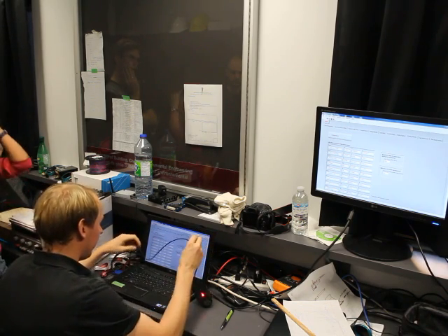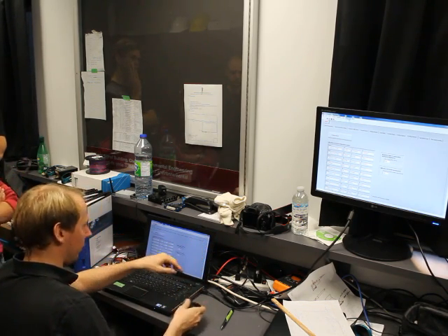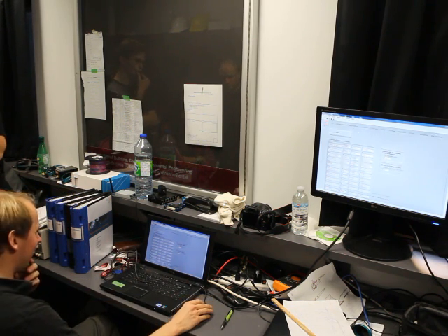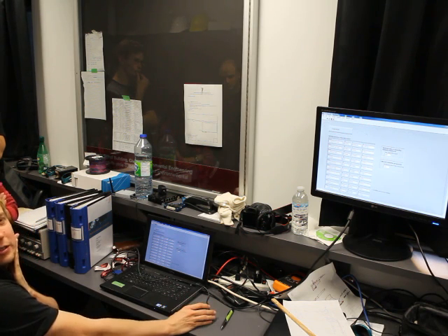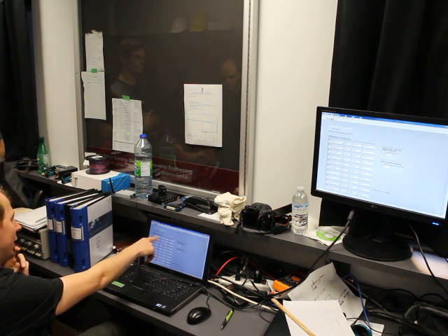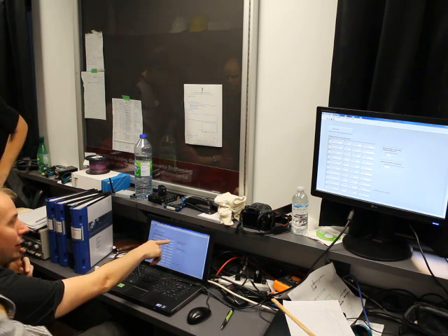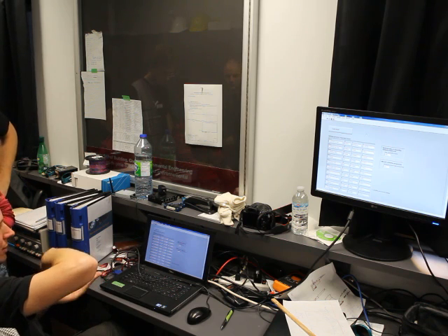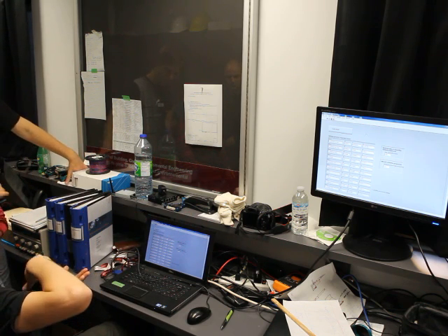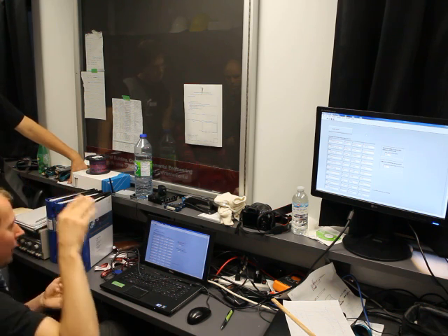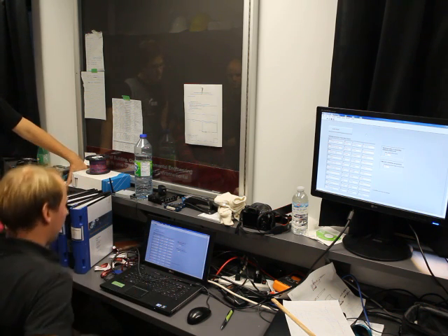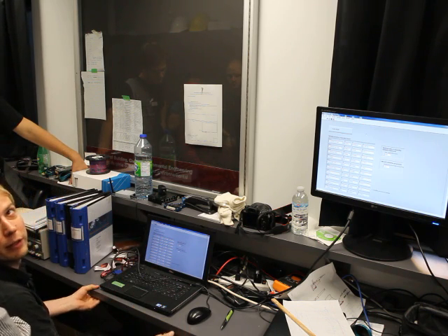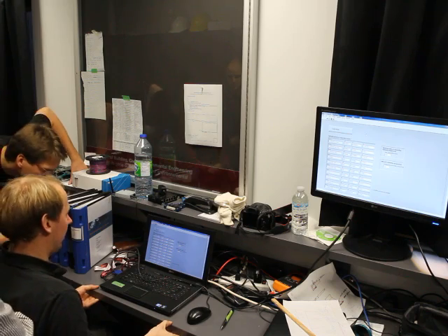What is also maybe important is we already talked a lot about calibration. You can calibrate your sensors, and what will come up is a value for R0, A, and B. This is how it's defined. It's a polynomial regression, a second-order polynomial, and you will get values for R0, A, and B, and you can put them in there.